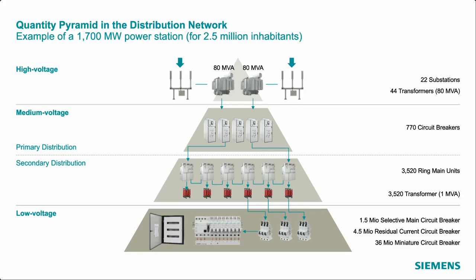In secondary distribution, we will have a total of 3,520 ring main units to distribute the power in smaller groups. Downwards, below each ring main unit, we will need one transformer with a capacity of 1 MVA. It means we will have the same number of transformers as ring main units. The purpose of these transformers is to step down the voltage once again, but now from medium voltage to low voltage and reach the final consumers.